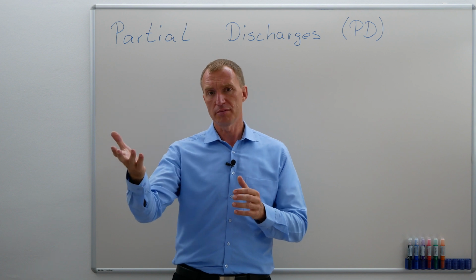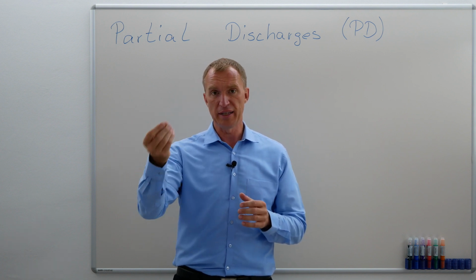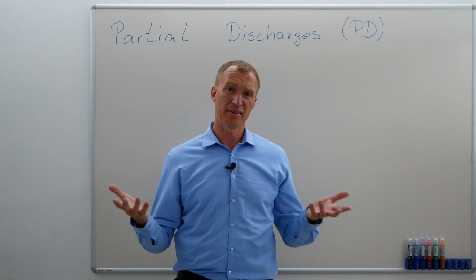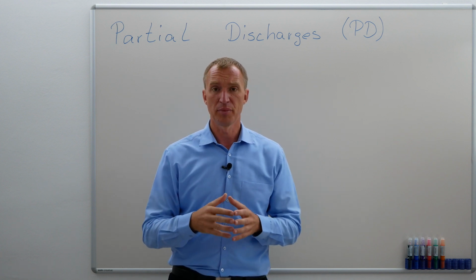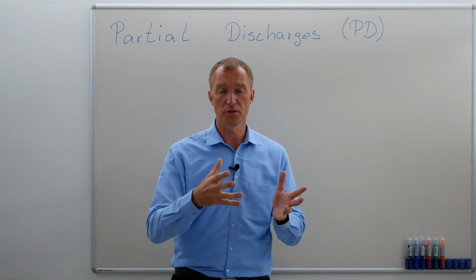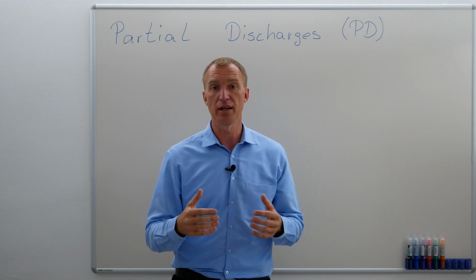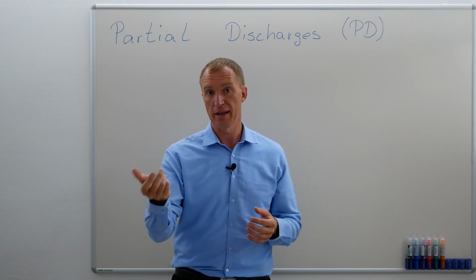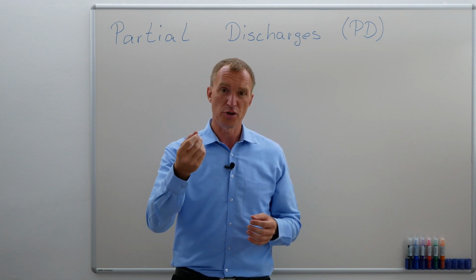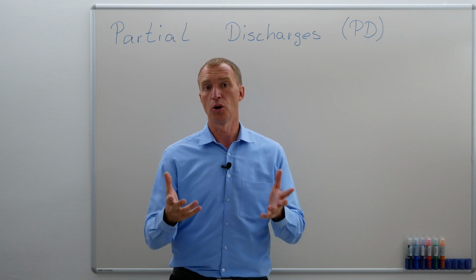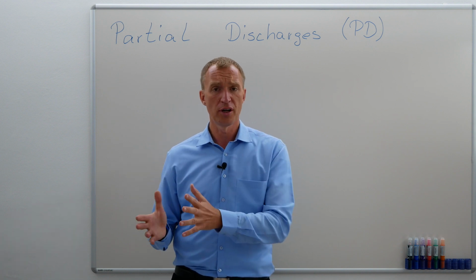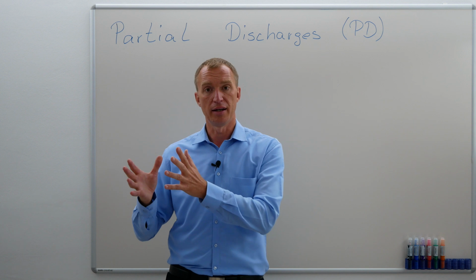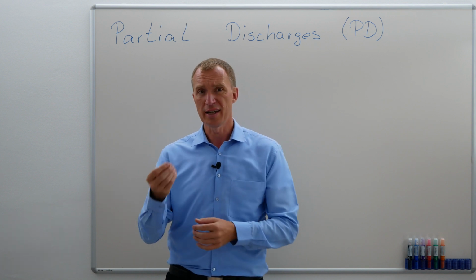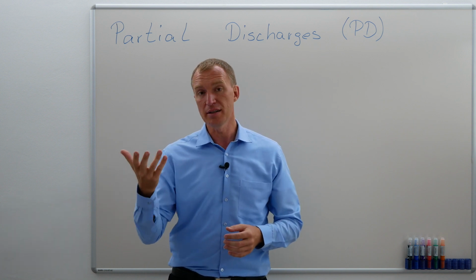Technically, you could see partial discharges because they emit light. However, in broad daylight, very often this is kind of difficult, but if you are close to sunset or sunrise, or you're in a room where you can dim the light, you can see partial discharges, external ones at least. They have a certain bluish glow and they're called corona. Furthermore, very often it's accompanied by an acoustical noise. It's sort of a hissing sound and you can hear that as well.